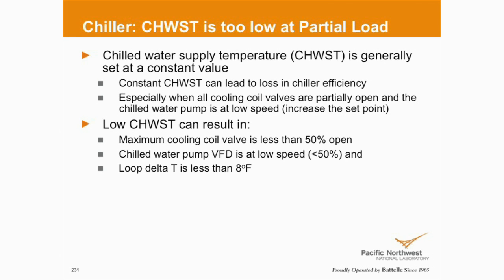If my cooling valves are starting to close off on air handlers — either because they're shut down, because loads went away at night, people turn lights off, or turn their printers and computers off — some of those loads go away along with solar gain at night. Those nights, weekends, shoulder months, and wintertime are times of day and seasons where chilled water reset may have some application to your plant. If you've got a plant serving lots of buildings and it's the tail wagging the dog — one building that needs 40-degree water year-round, like a vivarium, a lab, or a data center — you're probably stuck. But you've got to get creative. Maybe it's a 2-degree reset instead of an 8-degree reset.